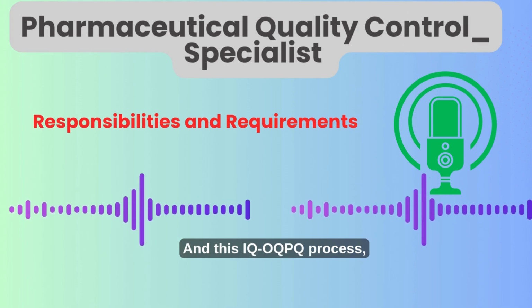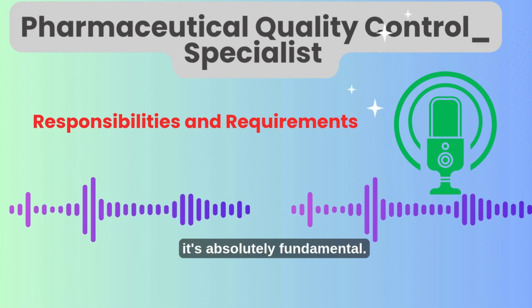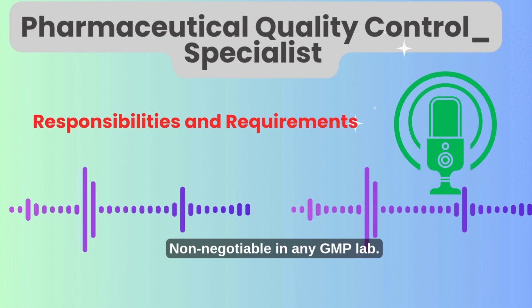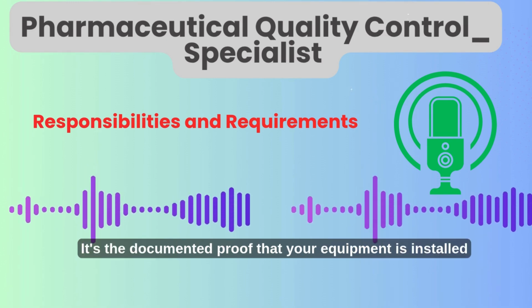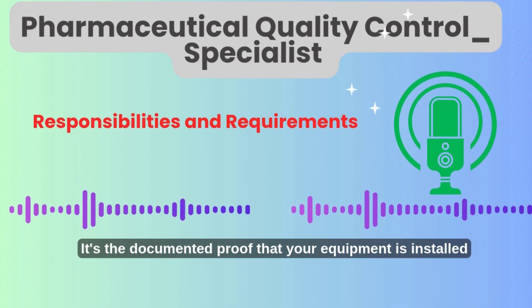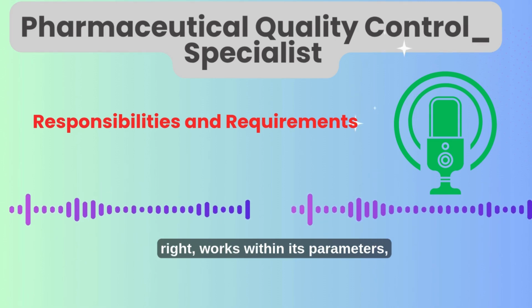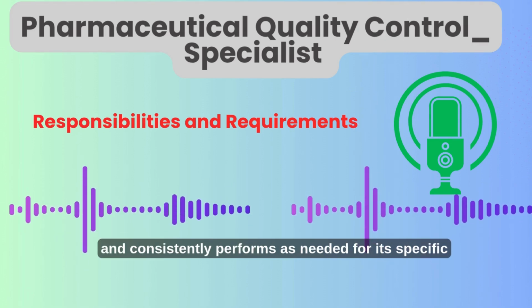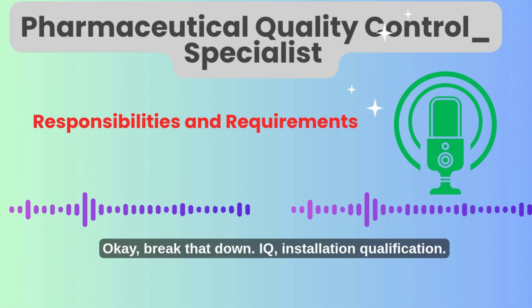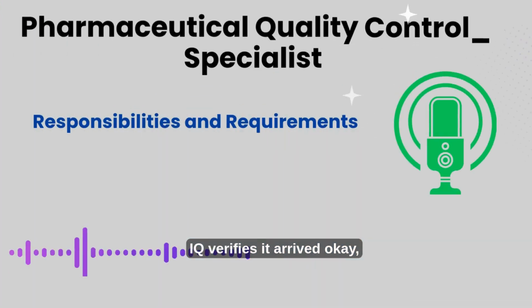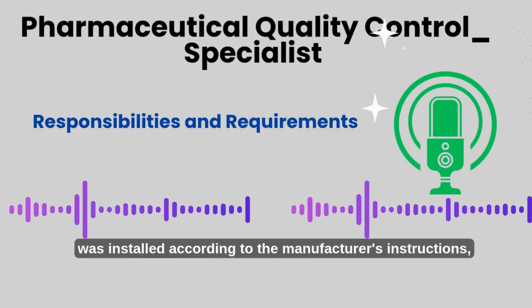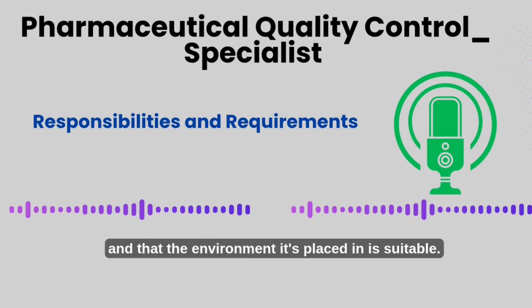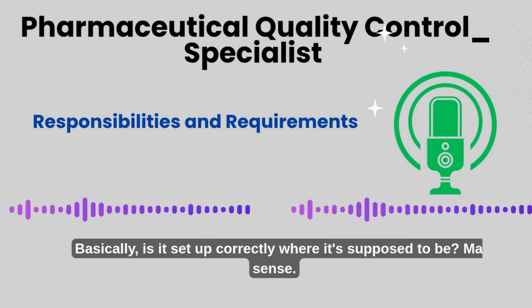And this IQ-OQ-PQ process is absolutely fundamental, non-negotiable in any GMP lab. It's the documented proof that your equipment is installed right, works within its parameters, and consistently performs as needed for its specific job. Okay, break that down. IQ, installation qualification. IQ verifies it arrived okay, was installed according to the manufacturer's instructions, and that the environment it's placed in is suitable. Basically, is it set up correctly where it's supposed to be?